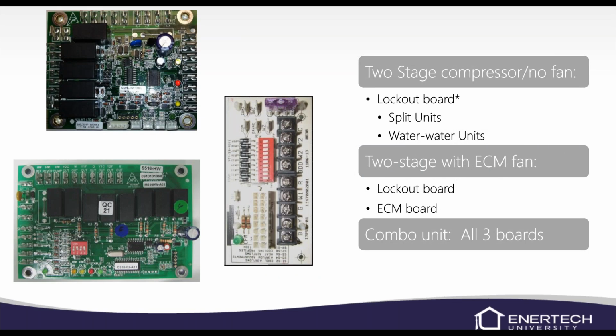So basically, if you have a 2-stage unit, it could be a single stage too, it doesn't really matter, but with no fan in the unit, like a water-to-water unit, then that's only going to have a lockout board. That also includes the split units. Any units that have an ECM fan would have a lockout board and an ECM board. Then we have the combination unit, which is a water-to-water and a forced air unit, and that would have all 3 boards. All of our units will have a lockout board in them, and then depending on the other functions of the unit, we would either have an ECM board and a combo board as well.